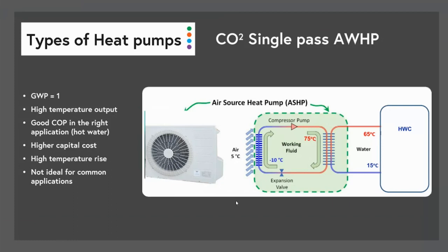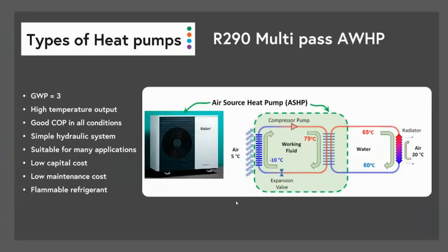It also can't do central heating. We don't use big temperature lifts like that in central heating. We do small temperature rises of 5 to 10 degrees, which are maintaining a system. So CO2 heat pumps are not suitable for central heating applications. So let's then move along to the next type of heat pump.